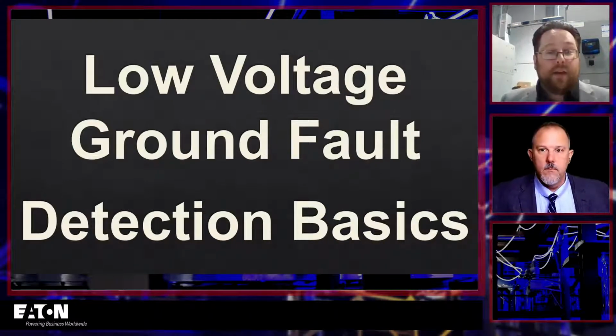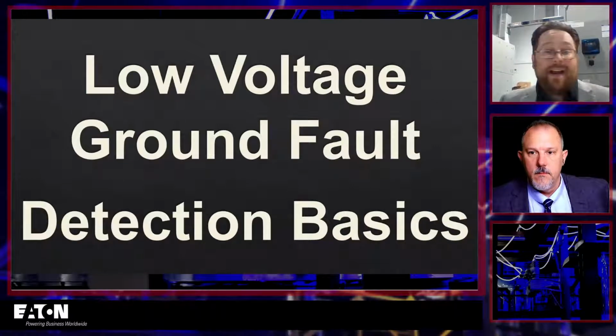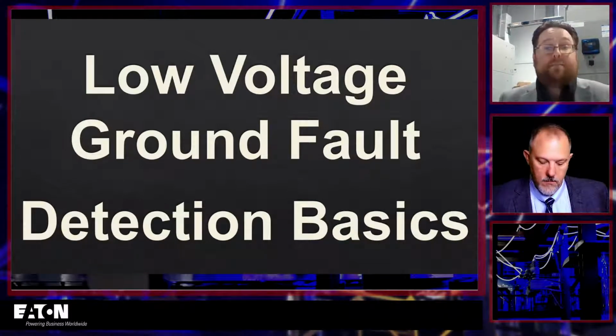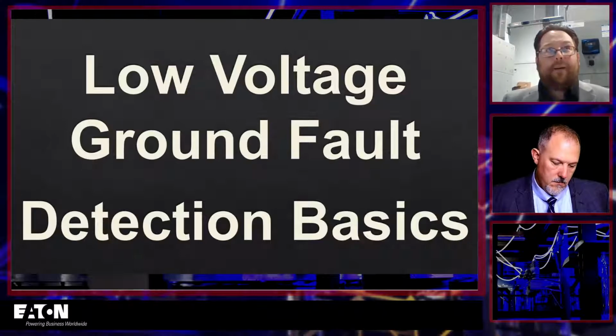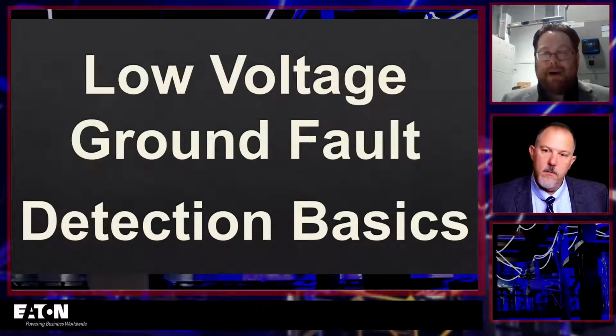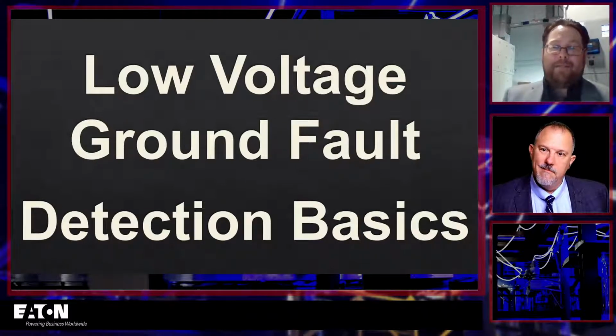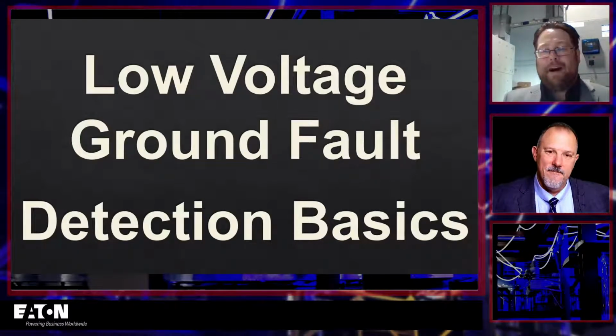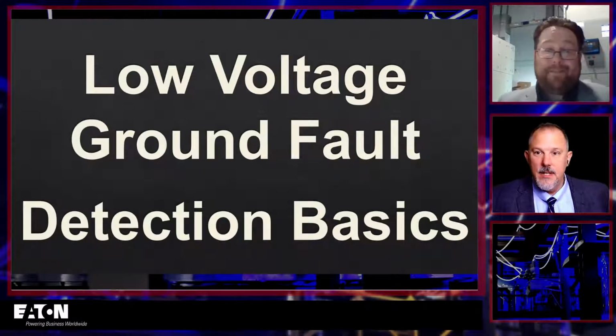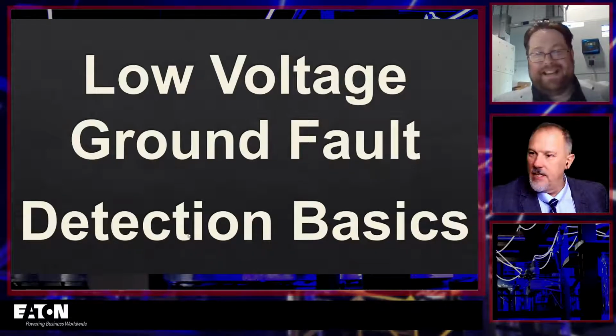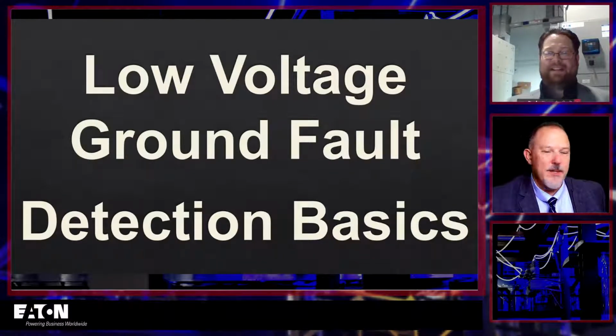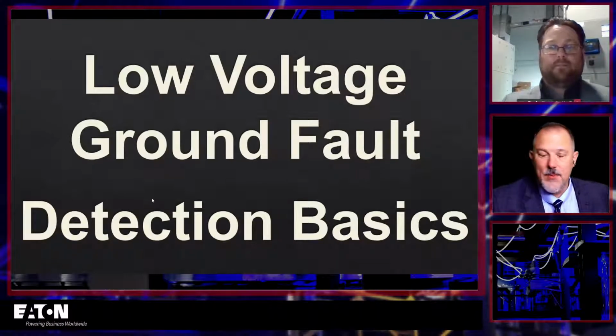Now, as the owner of the equipment, you could choose to go above and beyond, and that's not necessarily a bad thing to do ultimately to prove your system. Because, coming from a power systems engineering background, doing arc flash studies and coordination studies, I never got a phone call saying, hey Mike, I'm so glad your breaker tripped. Normally I would get a phone call saying, Mike, your breaker tripped, why did it happen? And we'd have to have that discussion about how the breaker tripped because it thought there was a problem, and if you had that real problem, that's what we want. Yeah, we call that shooting the messenger, right? Yeah, that's what happens. Typically nobody wants to hear the news.